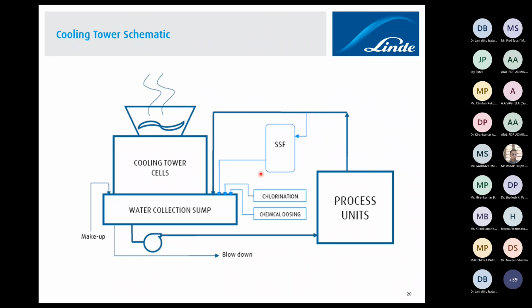So one terminology is called the LSI index, Langelier Saturation Index. That is one measure. That measure gives the corrosiveness of the water, whether the water is corrosive or not. Another thing is a biofouling monitor. Again, just like a side stream filter, you can take out one small stream. You can see what is the amount of bacteria present.